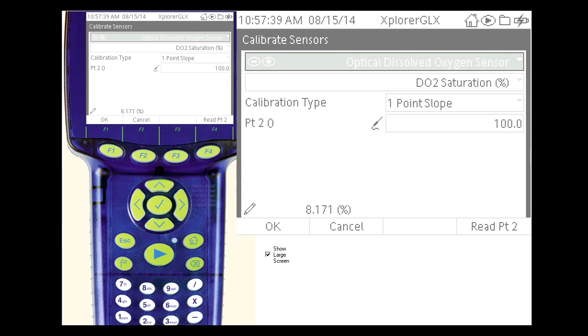This will be a 1-point slope calibration, and in this case the optical dissolved oxygen sensor is already selected. When the value has stabilized, select Read Point 2. The sensor has now been calibrated, and we can proceed with the lab.